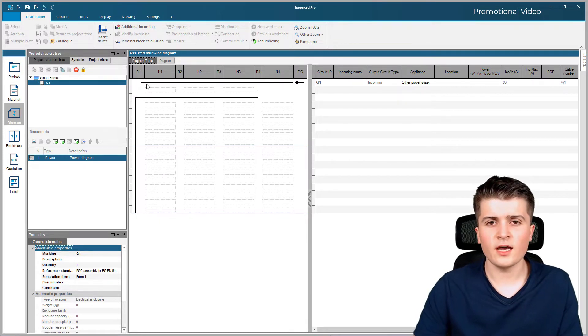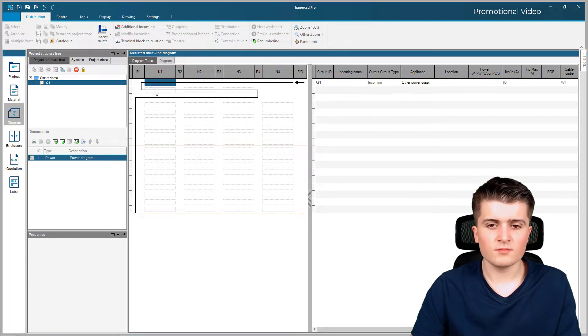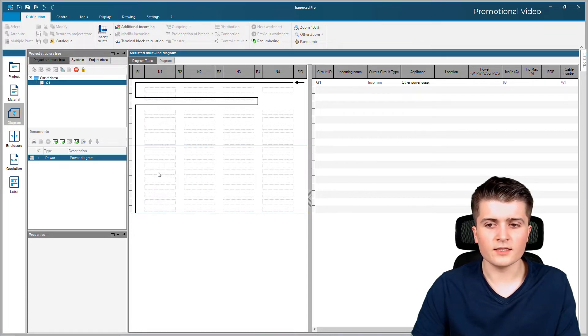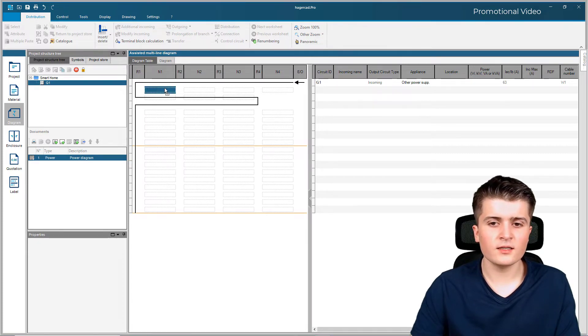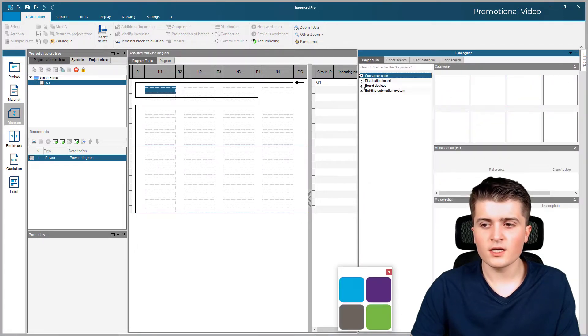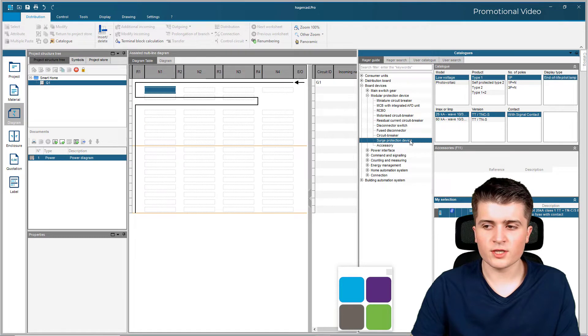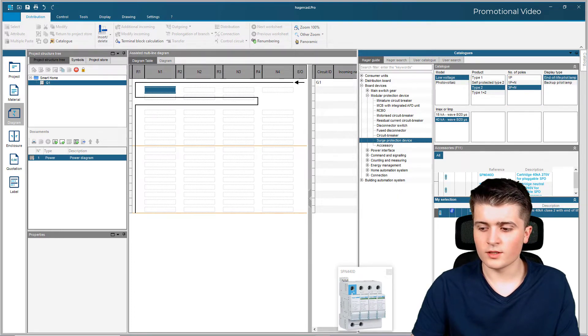The first device I want to add is the surge protective device, placed in front of my current loop. To place devices here I have to click on this corner, then right-click and insert new lines. With that we get a new line where we can set up devices. I click on field N1, go to the catalogs page, and find it under board devices, modular protection devices, surge protection device. I will use a type 2, three poles with neutral, and quickly add it.